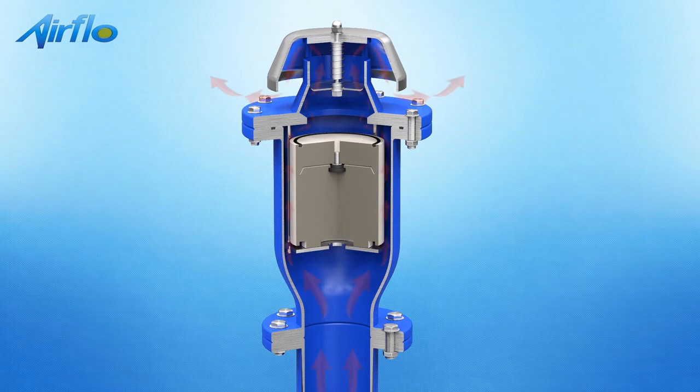This results in the uniform deceleration of the approaching water due to the resistance of rising air pressure in the valve. The magnitude and amplitude of surge and water hammer is reduced more rapidly and more uniformly with the variable orifice principle than conventional anti-slam devices.